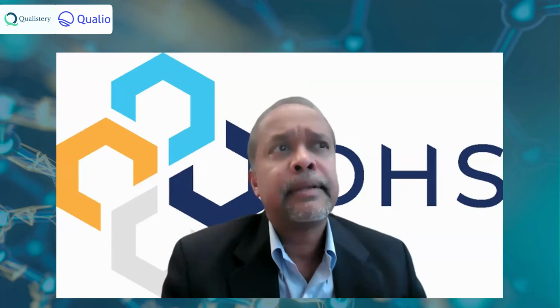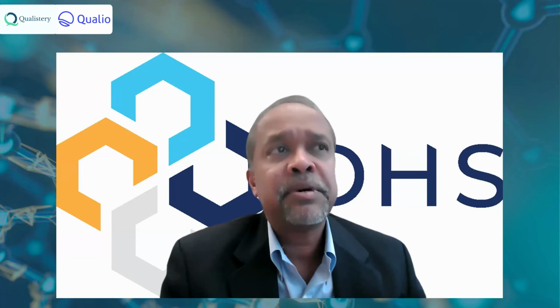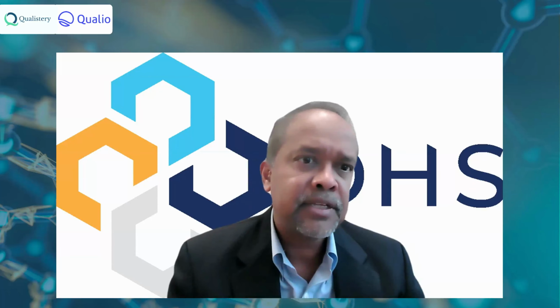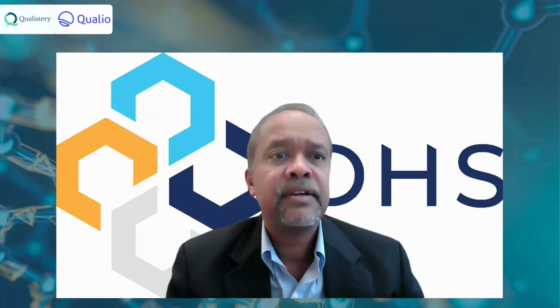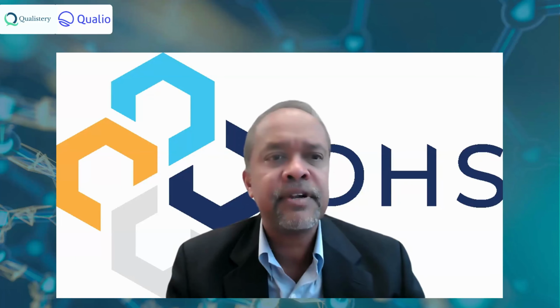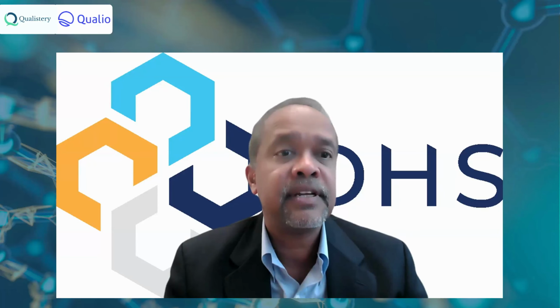So again, I'm not a leading expert in 60601, but as we work with companies like Intertek and SGS, etc., to do some evaluation for the standard and give us results, create a report for us, they do ask to review a risk analysis file, right?